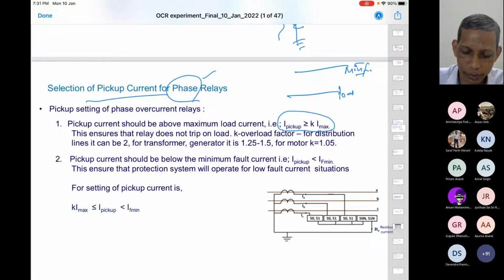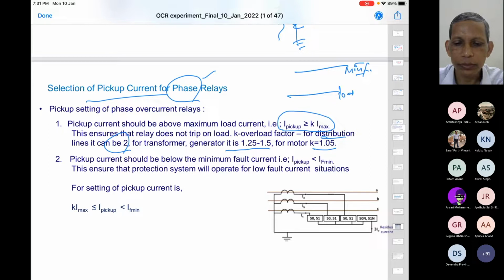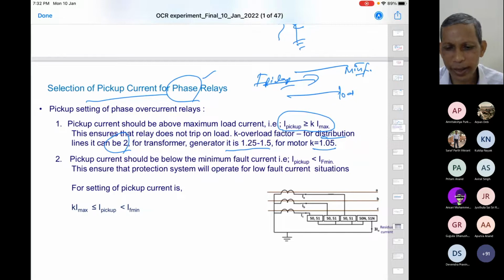So the general guidelines, the overload factor we call, for the generator it is 1.25 to 1.5 if we are protecting a generator. For a motor it is close to 1.05 times only the maximum current. But for overall distribution lines and all these things, it can be 2. So this study reveals, and with these kinds of things, the practicing engineers set the corresponding relay in terms of that. So if you are using it for a distribution line, you can use a factor of the maximum current expected in the system, and then accordingly twice of that will be a threshold for your pickup current setting in terms of that.